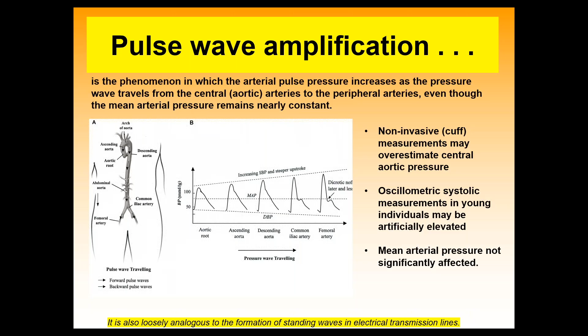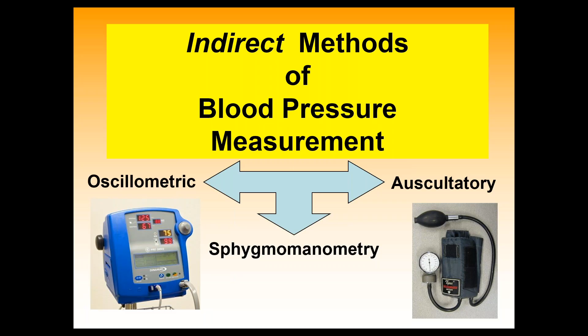Okay, now fundamentally, the whole point of this talk is to look at these differences. So we have two fundamental indirect methods of blood pressure. And I don't even like using the word measurement because we're going to see shortly that it's almost a misnomer. The conventional cuff, we refer to as the auscultatory method just simply because we're listening with a stethoscope. We use a stethoscope to listen to lung sounds, bowel sounds. Those are all auscultatory, sound-based tools. And the oscillometric method, with our Dinamaps and our general machines, are also indirect measures. Collectively, they're referred to as sphygmomanometry. The key thing, though, is keep in mind it's an indirect measure.